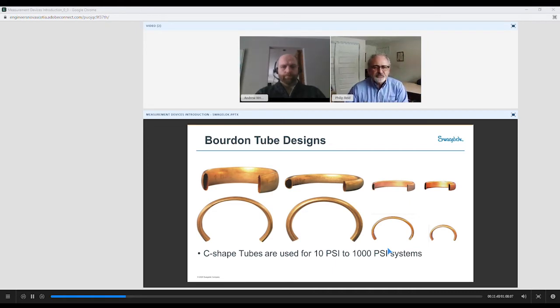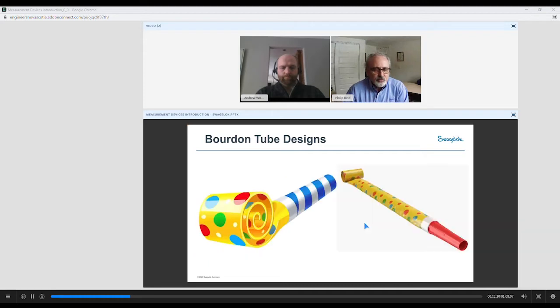Inside a pressure gauge, and specifically a Bourdon tube pressure gauge, is a C-shaped tube, and what this is, is just a round tube that's been flattened, and these tubes are used in pressure gauges from 10 to 1,000 psig. And again, that would be based on the wall thickness, and these are various materials. They can be stainless steel primarily in all of our pressure gauges. Copper shows up nicer on the slide, so we have copper here. They can be Monel or other exotic alloys depending on your application. So we use the C shape in the 10 to 1,000 psig range.